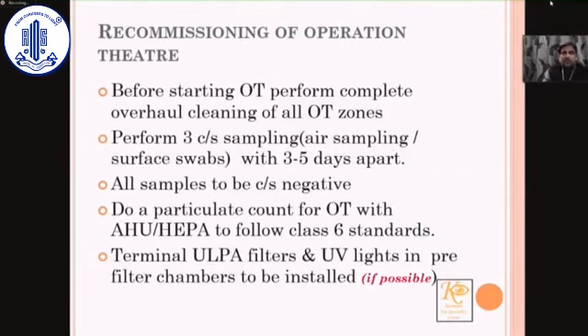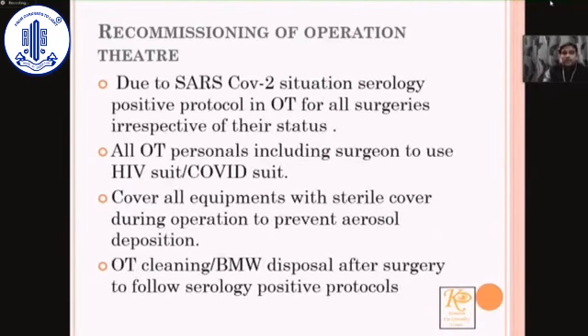Before starting an OT, make sure you completely clean all the OT zones and perform 3 culture sensitivity samples, 3 to 5 days apart. All of them should be culture negative. Do a particulate count for your AHU. Try to change them to ULPA filters and UV light in the pre-filter chambers if possible. And due to the SARS-CoV-2 situation, follow the serology positive protocol in the OT for all surgeries, irrespective of the status.